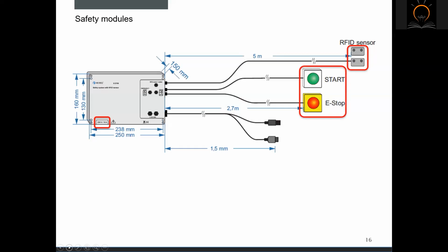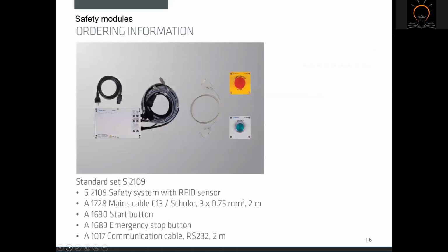Then we can find remote start, enabling execution of test sequences, or triggering back the emergency system in case the emergency stop was pressed. Of course, we can also find the emergency stop here, and a connection cable with connector to be connected on the front panel of the test instrument. The standard set of such a safety module is as follows. Each safety module has the safety device, connection cable, main supply cable, and start and stop button.